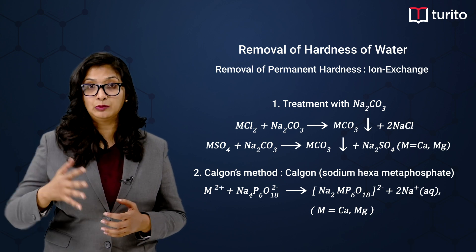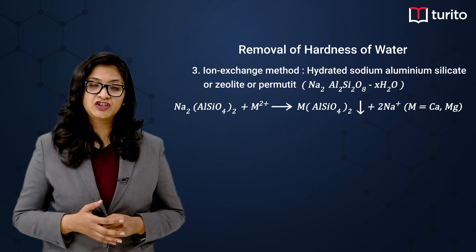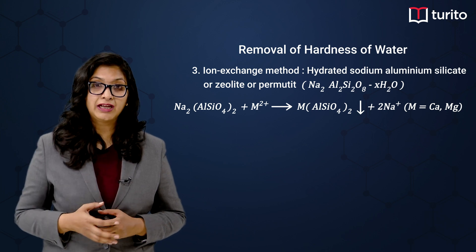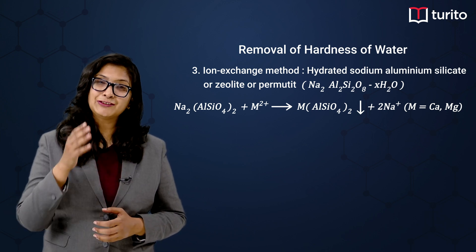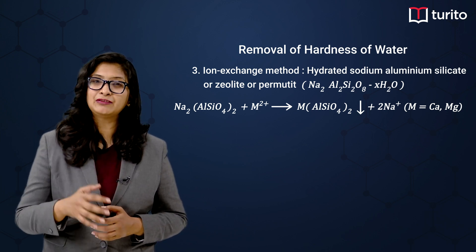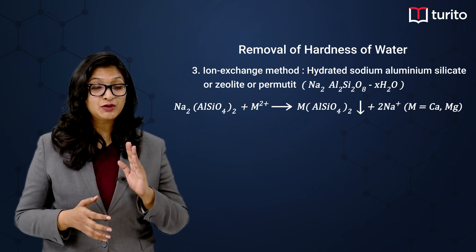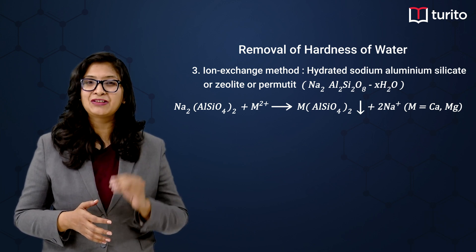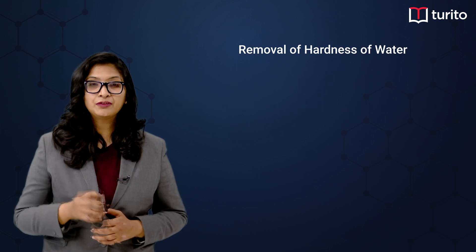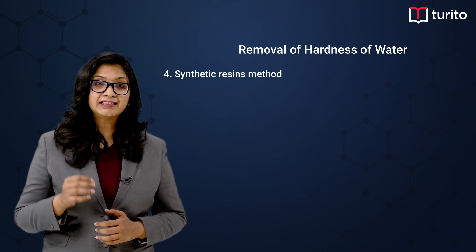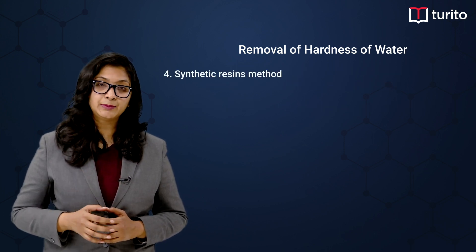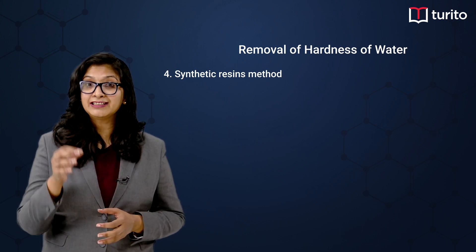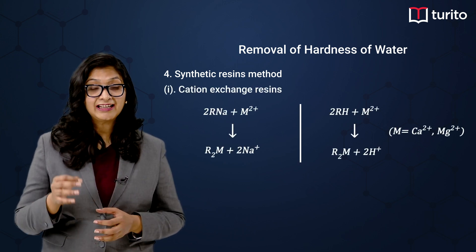Next is the ion exchange method, in which we use zeolites. In zeolite also, there is sodium present which will be exchanged with the magnesium and calcium in the water. Next is the synthetic resins method, which has two different sub-methods: the first one is cationic exchange.